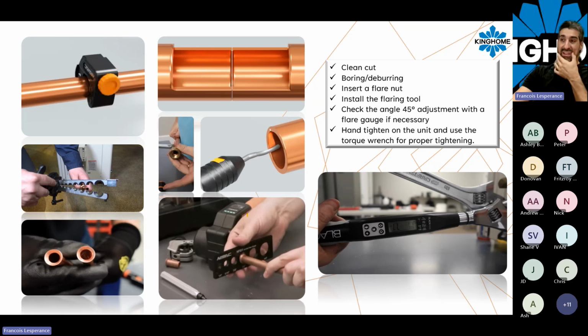Don't forget, when the flare is done, to give it a look. Take time to take a good look at what your flare looks like. See if the flare nut is sliding easily to the end and you don't hit the threads on the inner portion of the flare nut. Take a look at the portion here, the 45-degree angle that you've just created. Make sure there's no scratch, nothing here that can cause you a leak.